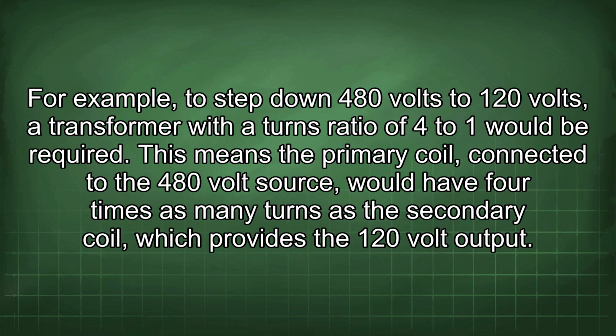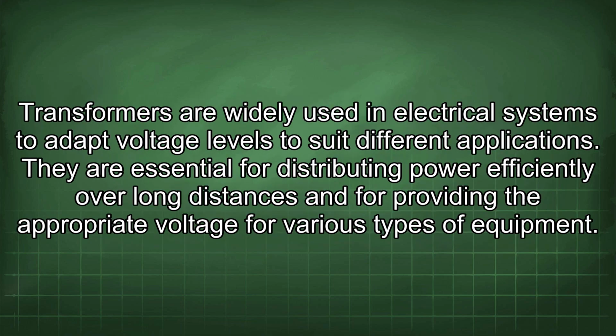For example, to step down 480 volts to 120 volts, a transformer with a turns ratio of 4:1 would be required. This means the primary coil, connected to the 480 volt source, would have 4 times as many turns as the secondary coil, which provides the 120 volt output. Transformers are widely used in electrical systems to adapt voltage levels to suit different applications. They are essential for distributing power efficiently over long distances and for providing the appropriate voltage for various types of equipment.